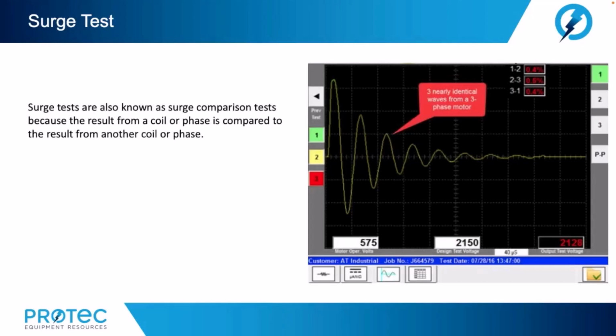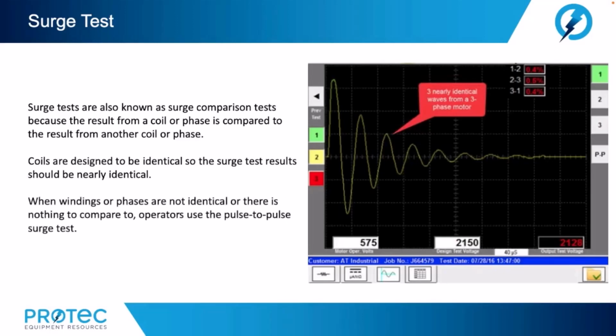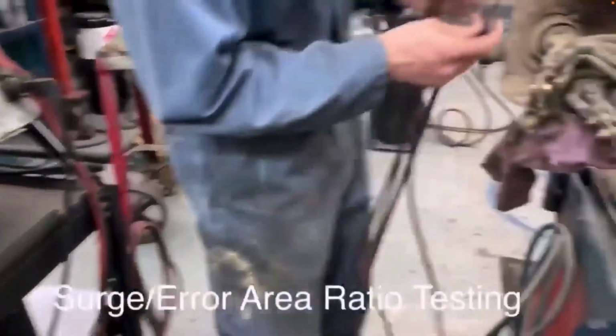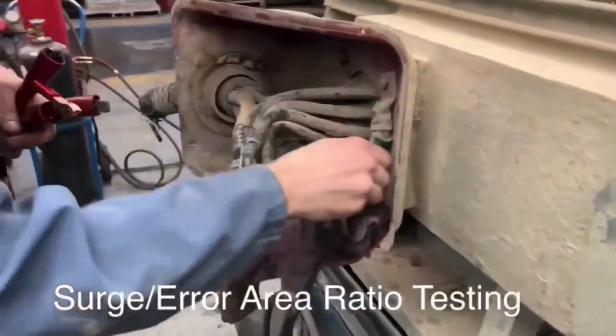Now, surge tests are also known as surge comparison tests because the results from a coil or phase are compared to the results from another coil or phase. Coils are designed to be identical, so the surge test results should also be nearly identical. When windings or phases are not identical or there is nothing to compare to, operators use the pulse-to-pulse surge test. But let's look at how a surge tester works.